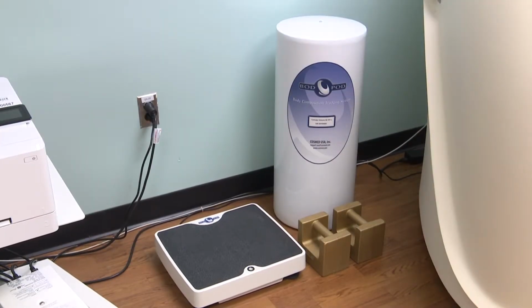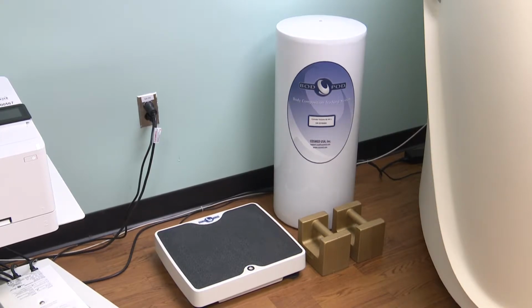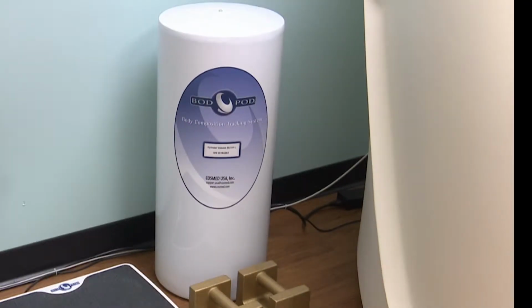Next, there is a scale. This scale is calibrated prior to each use of the Bod Pod screening. Beside the scale are weights that are specifically weighted for calibration. These weights have a combined weight of 20 kilograms. Behind the scale is the calibration tube. This tube has a known factor for weight, size, and density when calibrating the Bod Pod itself.